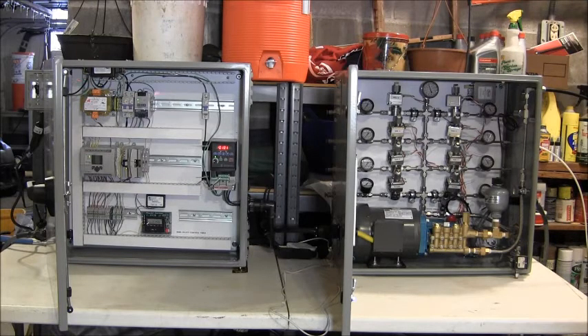Now, we'll go over just the input assembly a little bit here. Power wire comes in over at the left. Up on top here is a surge suppression unit, a transient voltage surge suppression unit, TVSS, to eliminate any spikes that might come into the unit, a little bit of protection. This is a control transformer, 120 volts in to 24 volts AC out. That powers the solenoids. The solenoids are 24 volts AC. We've got a couple of power terminal blocks here, and a couple of circuit breakers. One of them is the main input circuit breaker on the left, and the other one is the transformer circuit breaker. And then over here we have a third circuit breaker, which goes into the variable frequency drive. Next here is a DC power supply. This is 24 volts DC, that powers this microcontroller here and its other I/O modules.